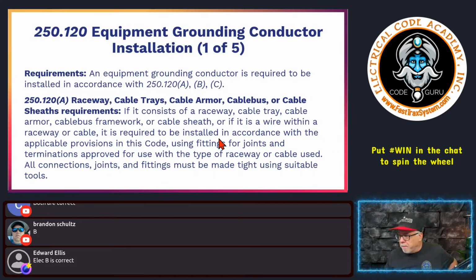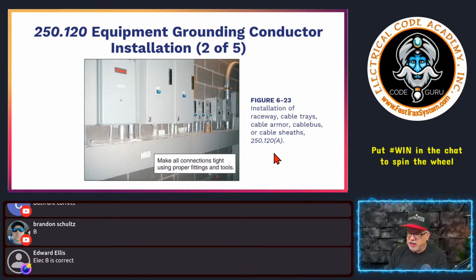All the fittings, everything. And so, by the way, if you buy EMT or rigid and use couplings, they're going to be fine. You buy the AC connectors for AC cable, they're going to be evaluated to work with the actual sheathing, all that type of stuff. So you're going to buy listed connections, listed fittings for use with the listed wiring method. That's pretty much going to take care of itself, okay? All right. So here you go. This is some examples. All connections are tight using proper fittings, okay? All of this could be used as an equipment grounding conductor if you choose. And again, most engineers are going to say, I'm going to put a wire type in there, but this gutter right here would qualify as long as all these connections are made right. As long as you're following the rules in 250.96, right? You meet all that stuff, then you're going to be good to go. That type of scenario, right?